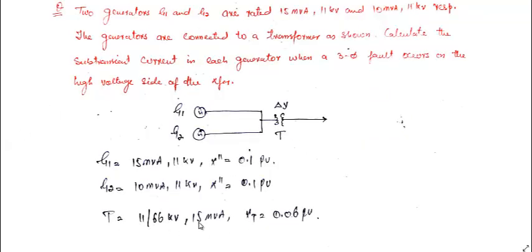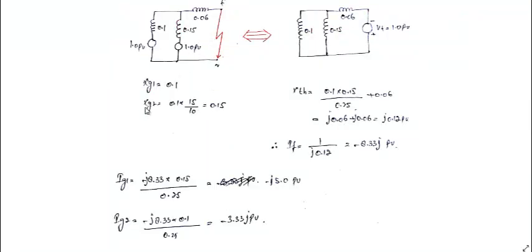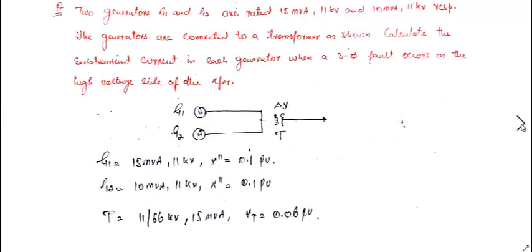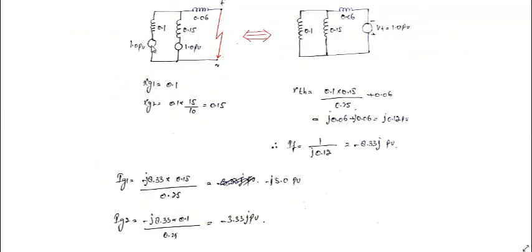In the per-unit equivalent circuit the reactances are: X1 = 0.1, X2 = 0.15, and transformer reactance = 0.06. Short-circuit the voltage sources. Since it is an unloaded system, pre-fault current I = 0. Before the fault, the fault point is open-circuited, so the pre-fault voltage Vt at the fault point equals the generator terminal voltage — 1.0 per unit angle 0 degrees.